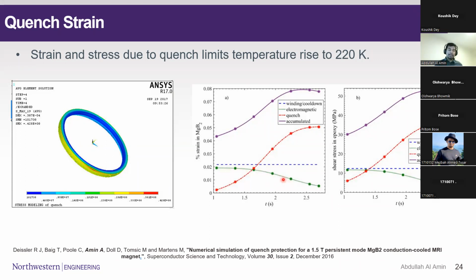As time progresses, when there is a quench, the magnet becomes partly resistive, and we do not want the electricity to pass through at exactly the same amount. So when we detect the quench, we have a detection system and protection system, which eventually drains out all the electricity, and that's why this green plot is going down.